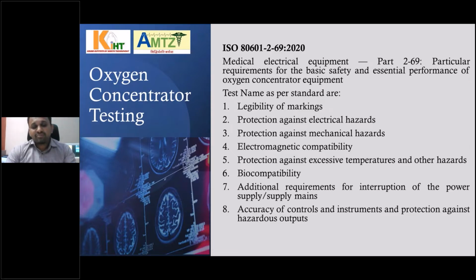And next is biocompatibility. We have the ISO 18562-1 standard, which applies to the parts, the accessories, and the gas pathways, where we check biocompatibility as they will be in contact with the patient or a human. So these are the particular tests, in general an overview of the particular standard applicable to oxygen concentrators.